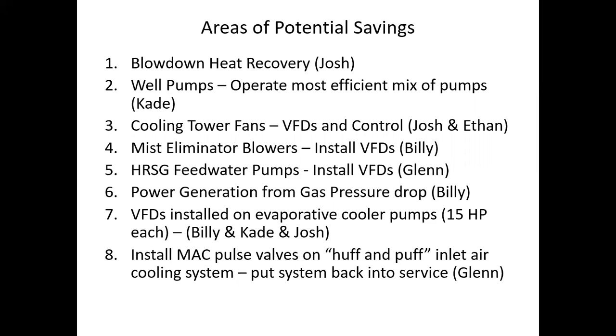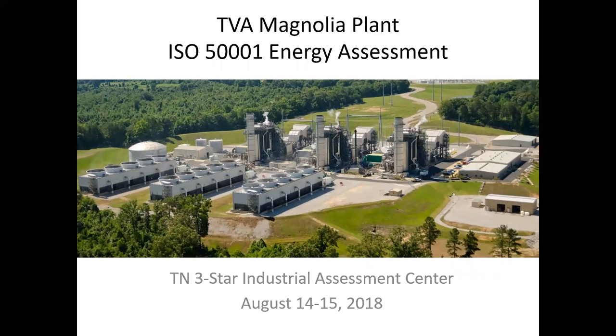When you take that fairly high pressure water, 1,000 PSI or so, and throw it to atmosphere, some of it flashes into steam. It's called flash steam. If you look at this picture, you can see these little plumes, these little white clouds coming out here. That's blowdown flash. Once that stuff flashes, it leaves the minerals behind, just like boiling it off. That's good steam you can recover and do something with.